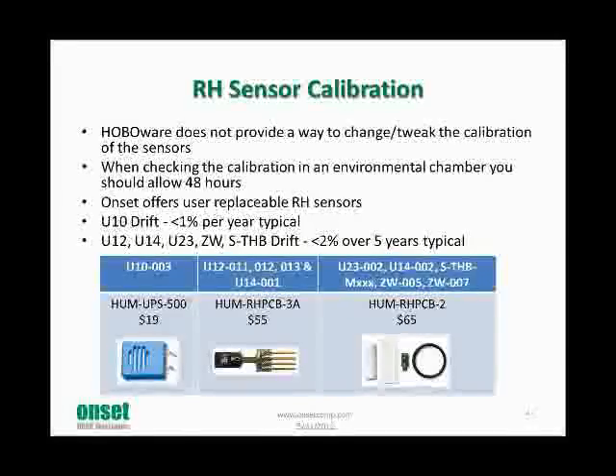So on the humidity side, HOBOware, the software doesn't allow you to go in and tweak the calibration of the sensors. Basically, what we recommend is that you check them. There are salt solutions, or if you have access to an environmental chamber and you want to check the sensors at different temperatures and humidities, you can do that.